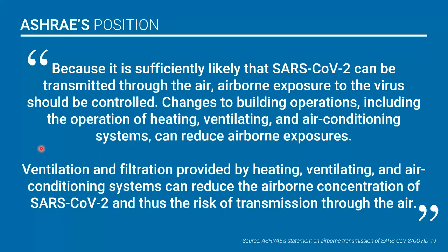So what is ASHRAE's position? Because we want to go back to science. And ASHRAE is saying, look, we do know that the viruses can be airborne. They can become a vapor, think of it as a fog, and it can get into an HVAC system. So they're saying ventilation and filtration provided by the HVAC systems can reduce the airborne concentration of the virus and thus the risk of transmission through the air. So one thing that's very important is no matter what we do to a ventilation system and a filtration system, it will not prevent person-to-person transmission. So all we can do is be as safe and conservative as we can in our designs.